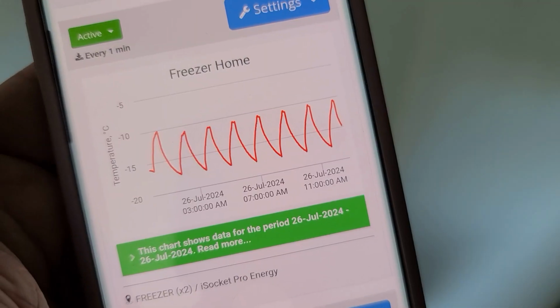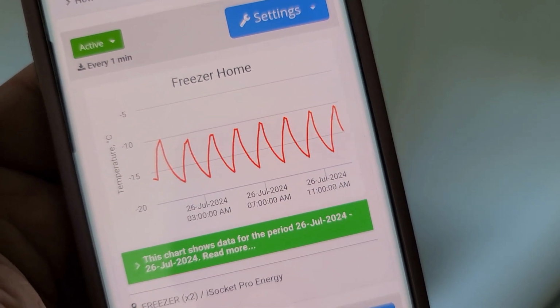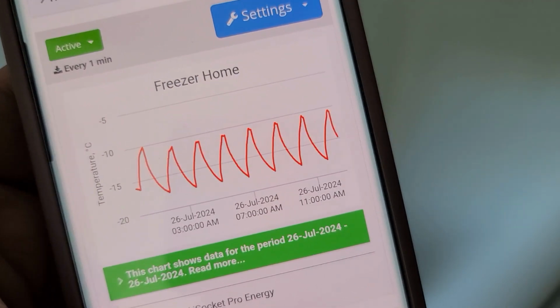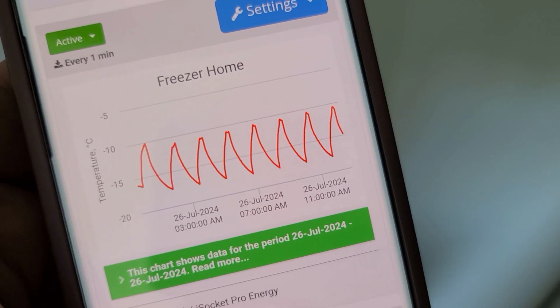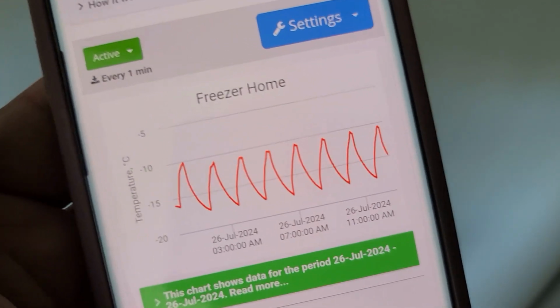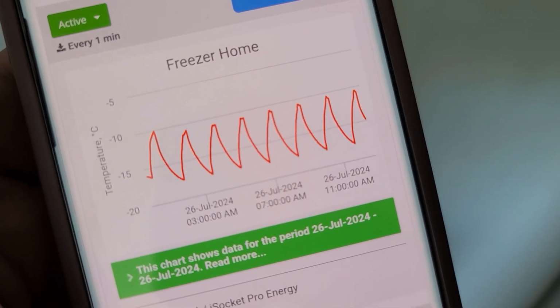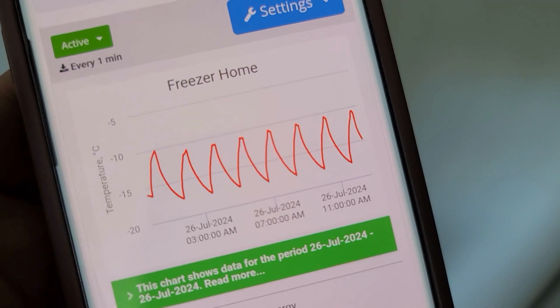I told you about faking the temperature on the freezer. On any freezer, it doesn't matter if this is a laboratory freezer or some very expensive freezer. They show you a faked temperature, the temperature that you set there. So here is an example. I have a home freezer where I now installed the sensor not that deep, closer to the door, sorry.